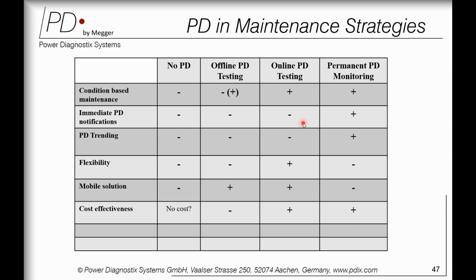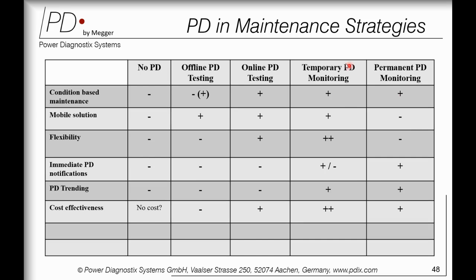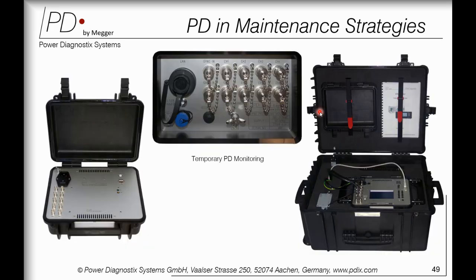So this was the monitoring strategy online, but now one more strategy has been added, which is temporary PD monitoring. What is temporary? It gives you the same condition-based mobile solution, with flexibility, immediate PD notification, PD trending, and cost effectiveness with the portable one. Earlier we were using the portable only for online PD testing, but now the portable will also help you with temporary monitoring. So now let's discuss in the upcoming slide what temporary PD monitoring is and how it's beneficial.